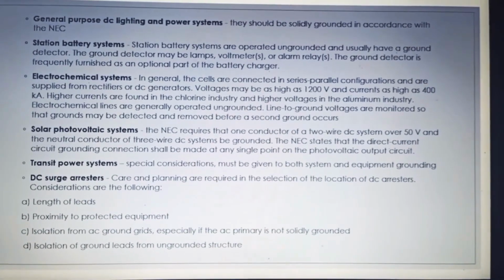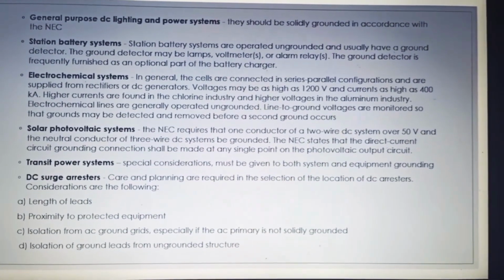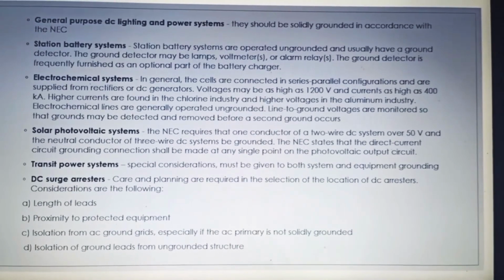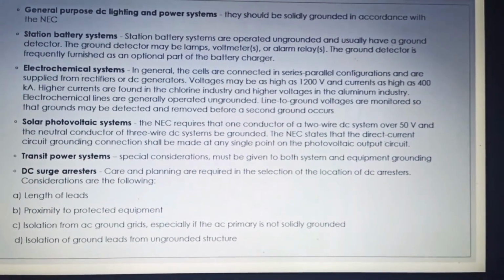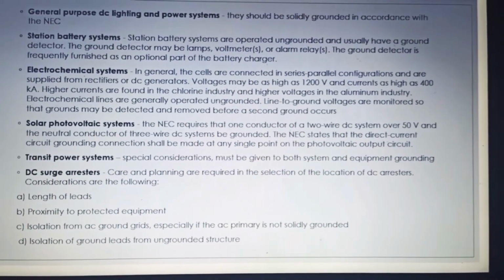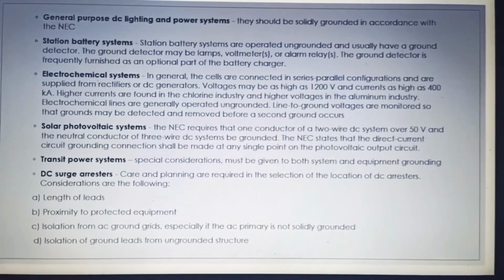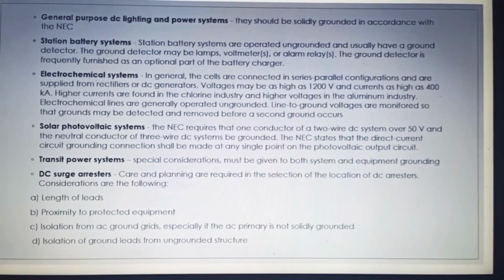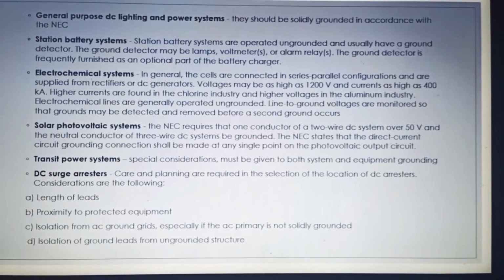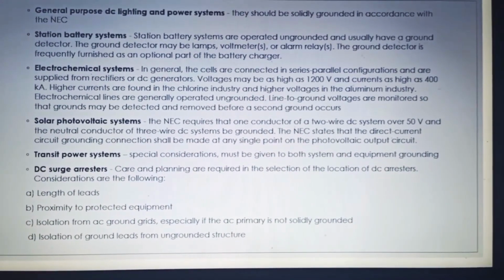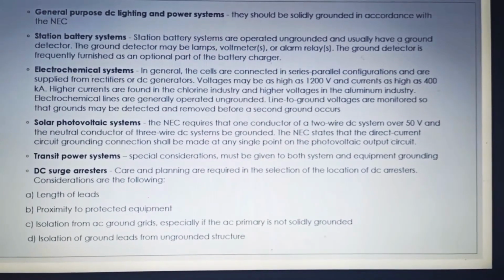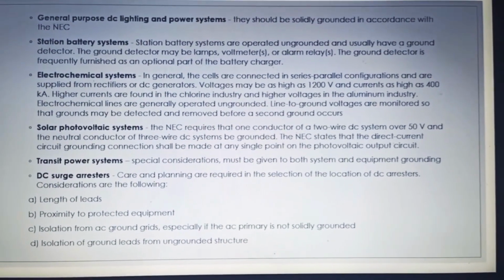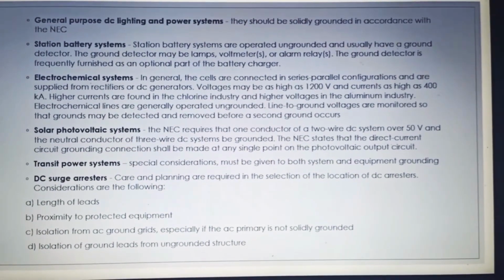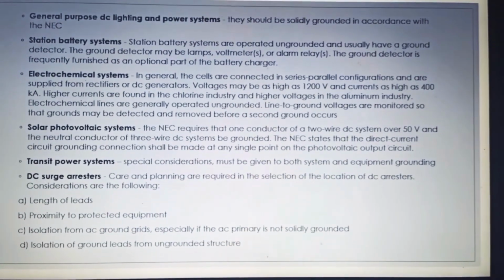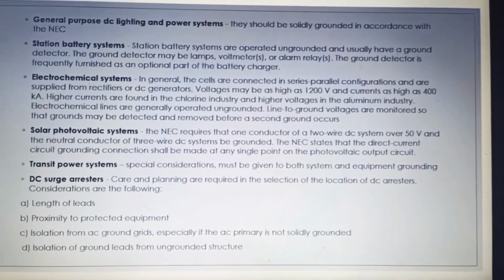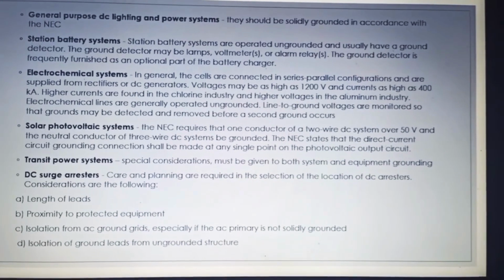Station battery systems. Station battery systems are used as a power control source for switchgear and process control equipment. In addition, the station battery may be used for emergency lighting or other emergency power requirements, such as bearing lube oil pumps for rotating machinery or valve actuators for critical valves. The battery systems are operated ungrounded and usually have a ground detector. The ground detector may be a lamp, a voltmeter, or an alarm relay. The ground detector is usually furnished as an optional part of the battery charger.